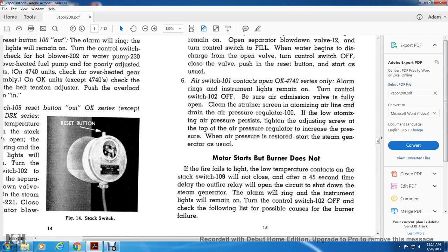Motor starts but burner does not. The fire fails, the low temperature contact with the stack switch 109 will not close after the 45-second time delay. The outfire relay will open the circuit breaker and shut down the steam generator. The alarm will ring. The instrument lights will remain on. Turn the control switch off.